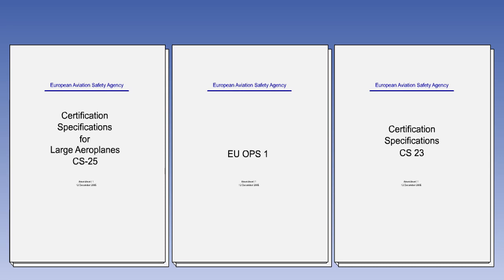In this lesson, we will look at the EU regulations appertaining to aircraft emergency lighting systems and we will see how these regulations are put into practice. The basic regulations are laid out in EU Ops 1, Commercial Air Transportation, Aeroplanes, with greater detail being provided in CS23, Normal, Utility, Aerobatic and Commuter Category Aeroplanes and CS25, Large Aeroplanes.